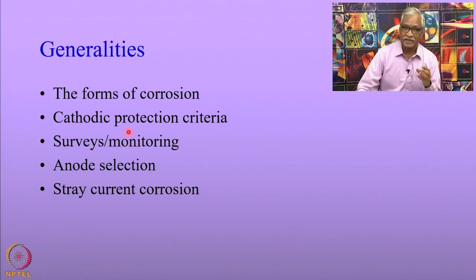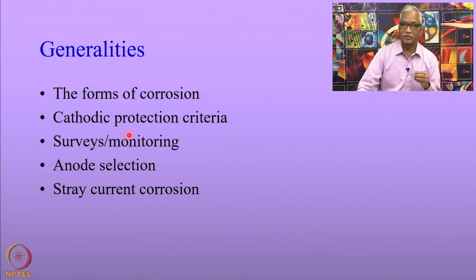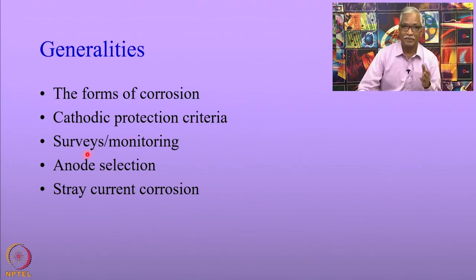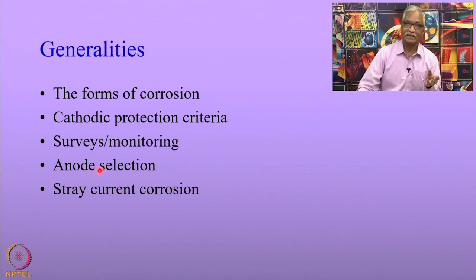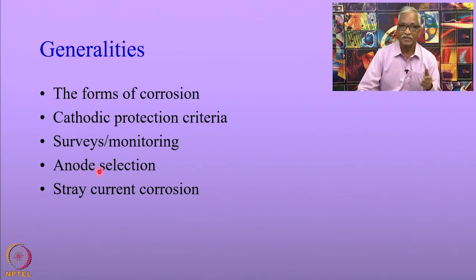The cathodic protection criteria applicable to pipelines are equally applicable to storage tanks. The surveys related to soil resistivity, pipe-to-soil potential, current requirement, and stray current corrosion are all applicable to storage tanks. The anode selection criteria and the way you calculate ground bed resistance are very similar to what is done for pipelines.